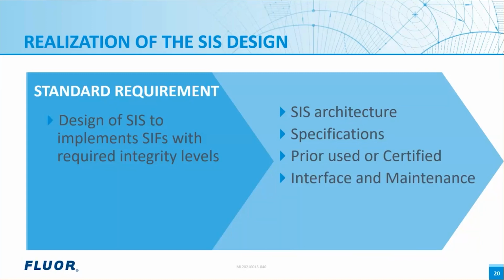The operator interface requirements include how SIS data is presented to the operators. Maintenance requirements include bypass and override philosophies. Carefully develop philosophies to avoid misuse of bypass for more availability. Limitations should be in place to prevent violation of the safety requirements.